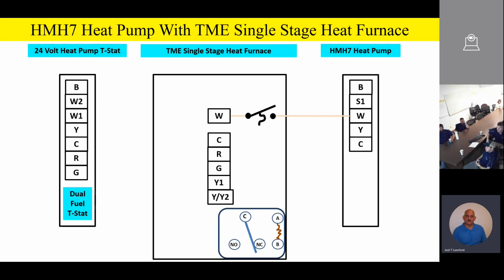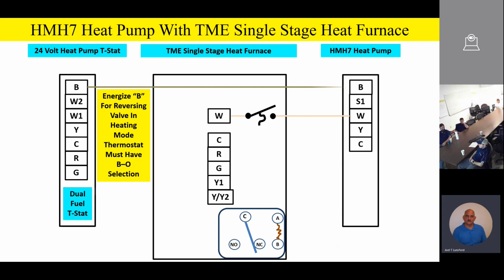So let's go ahead and pull that block wiring diagram. And as you can see, there we have that construction thermostat in the circuit from the W wire outside coming into the W signal inside on the furnace. We do have that construction thermostat in there, which is recommended for dual fuel application. In addition, you'll also notice that our thermostat is dual fuel capable. But just like we had before, team, we'll pick up the pace a little bit because it's essentially the same way. We're going to wire it just like we did before with an AE air handler, but it's a furnace this time.